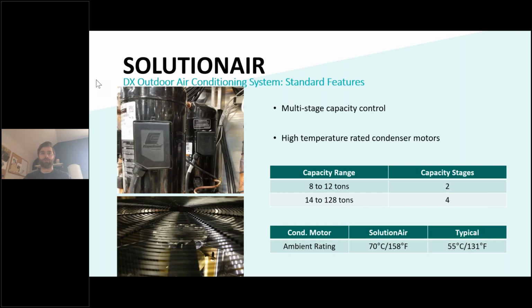For our DX offering, we go from 8 tons up to 128 tons. Always have a digital scroll leading compressor on there, so it's fully modulating throughout. But from 8 to 12 tons, you get 2 stages, and from 14 to 128, you get 4 stages of capacity there. Additionally, we standardize around a higher ambient rating condenser motor. So ours, its rating is 158 Fahrenheit. Typically, it's around 131. We find that with that higher ambient rating, those condenser motors have a little more longevity, which is a bonus for us in our eyes.